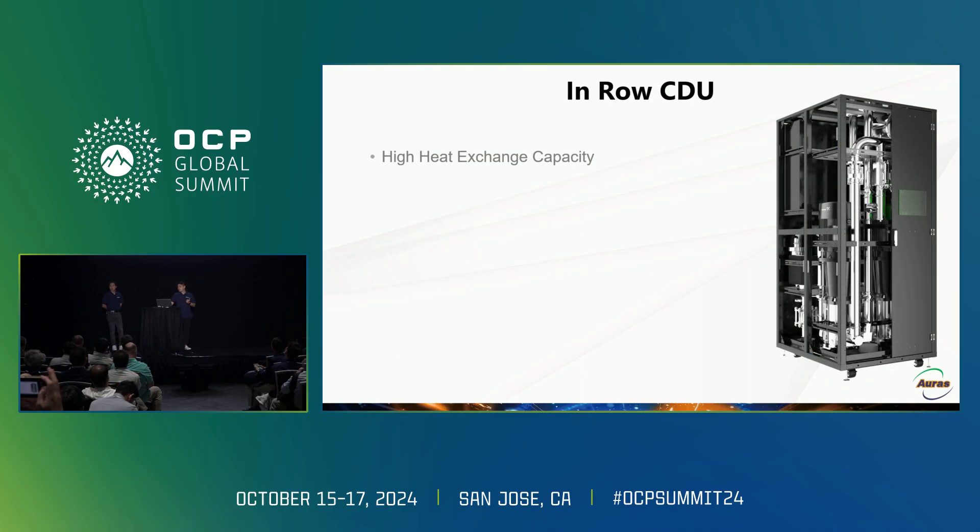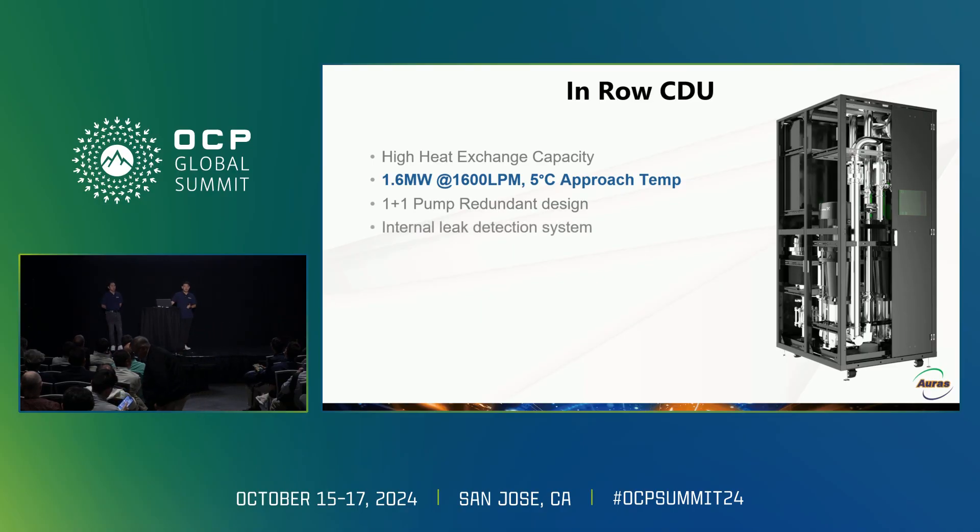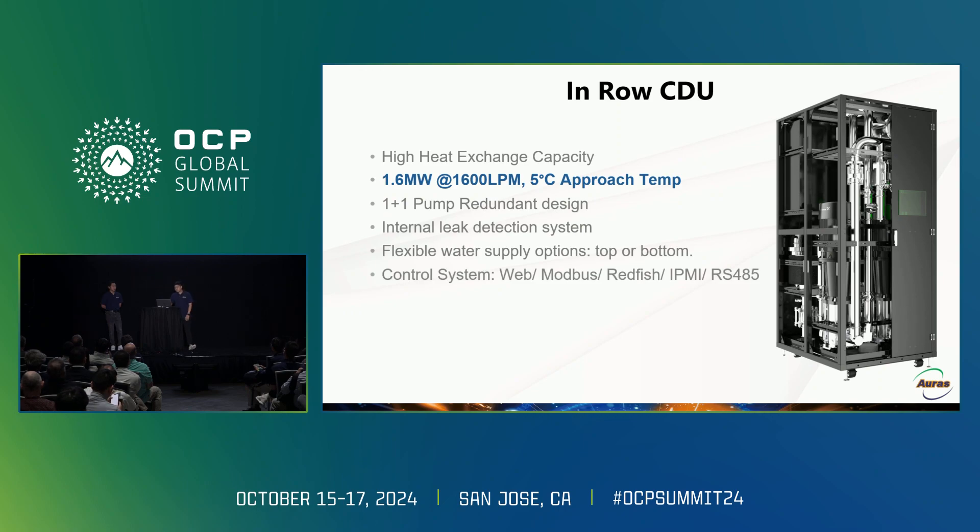For higher wattage demand, we recommend using the in-row CDU. Its cooling capacity can support up to 1.6 megawatts with 1,600 lpm at 5 degrees Celsius approach temperature. It has a 1+1 pump redundant design and an internal leak detection system. It also has a flexible water supply option from either the bottom or the top. The control interface includes web, Modbus, Redfish, IPMI, and RS-485.